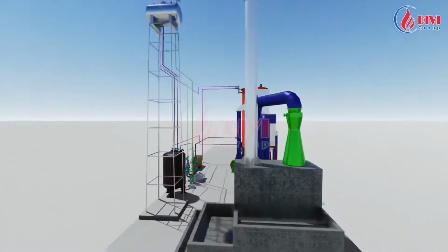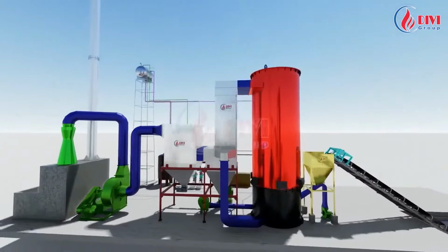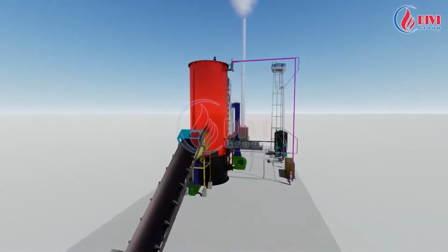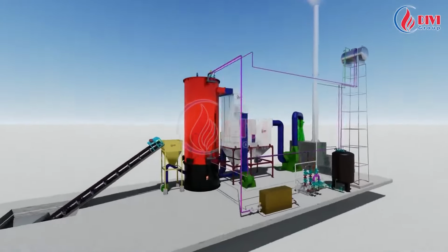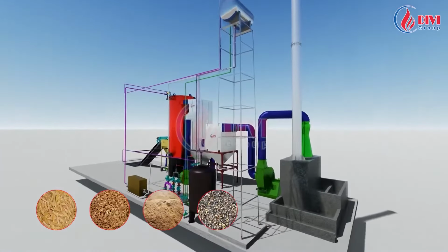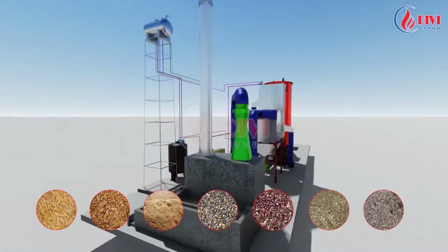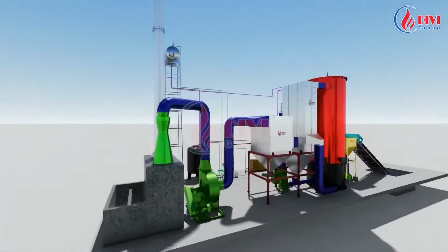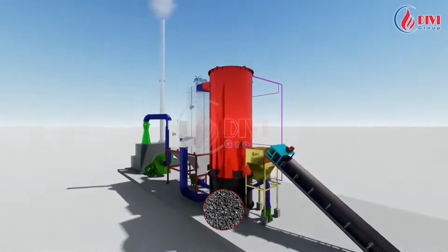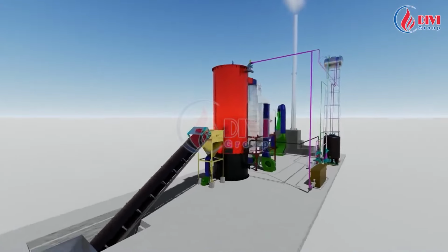Here I would like to present the operating principle of the biomass-fired fluidized bed thermal oil heater, designed by DIVI Boiler within the DIVI Group, as follows. First, I would like to point out some types of fuel that can work effectively for this fired fluidized bed thermal oil heater technology: rice husks, chopped firewood, sawdust, cashew residues, coffee husks, waste veneer, phloem, and so on. In addition, the fluidized bed thermal oil heater can also use fossil fuels such as coal bran imported from Indonesia.